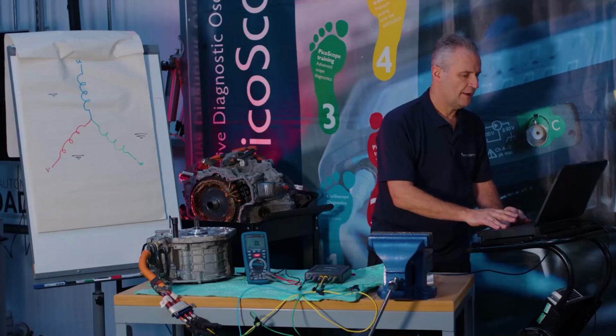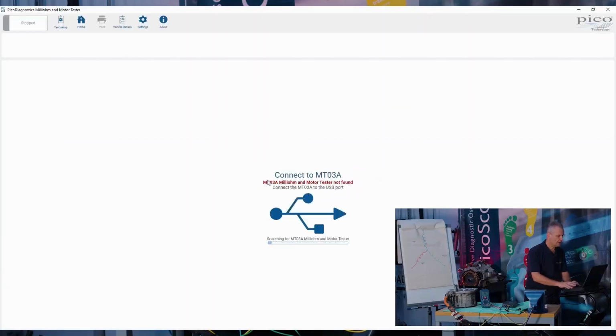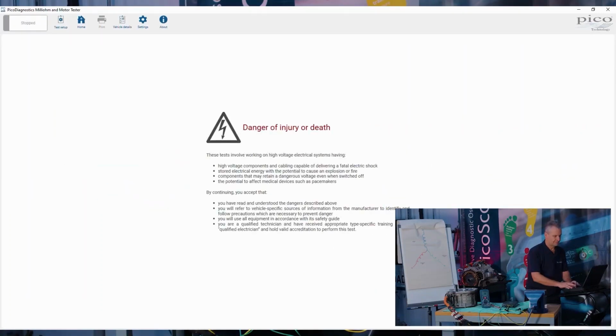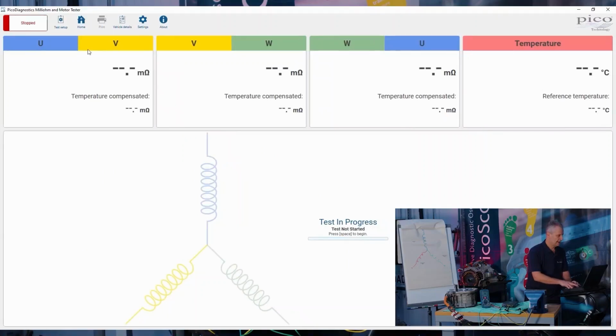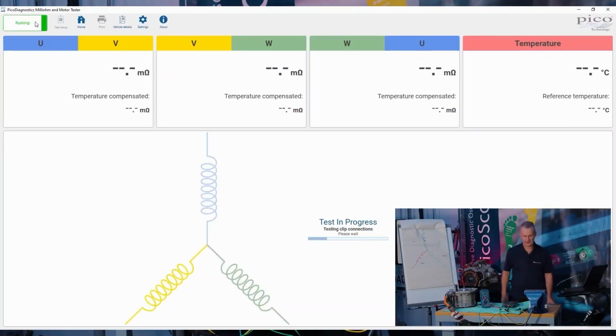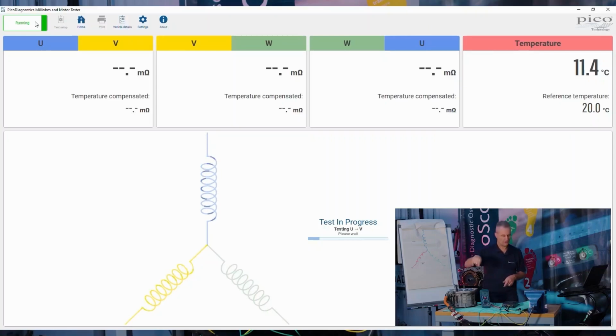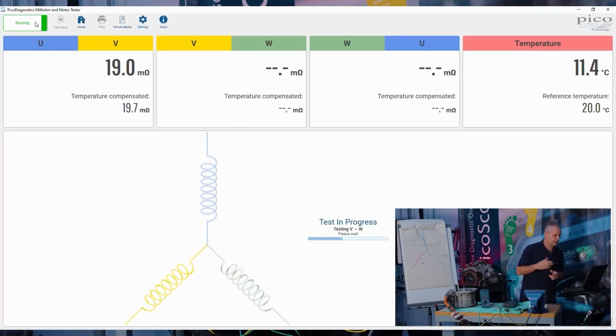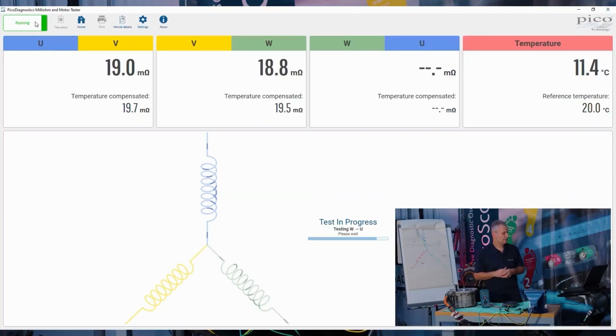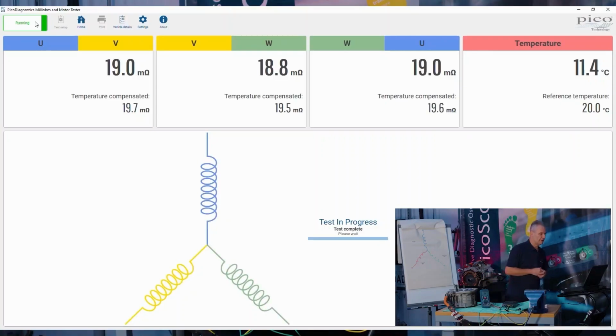We'll open up the Milliohm meter software and click on electric motor test. Accept the warning, and this pretty much is as straightforward as it gets. Just notice in the pictogram here that we test by passing current through the winding. We start with U and V. We then reverse that current, which allows for any thermal EMF effect from differential metals being connected via crock clips, etc. And finally, we come to the last phase, W to U. And there we have it, a balanced motor.